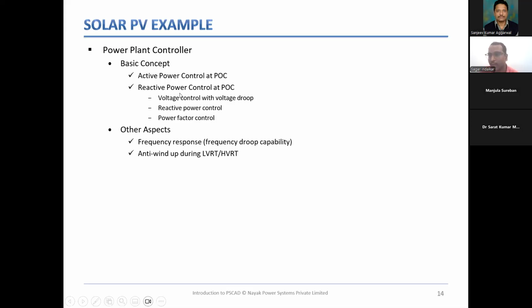Apart from that, it also has to supply reactive power. It has to provide reactive power support. Based on the requirements, typically the voltage requirements, a PPC has voltage control, voltage droop control, reactive power control, and power factor control, so that it can operate at certain operator inputs. For example, to inject Q to obtain a certain voltage. Then there is power factor control as well, where you can ask the PPC to operate the plant at, let's say, 0.99 power factor. Correspondingly, it will generate more Q so that that power factor is attained.